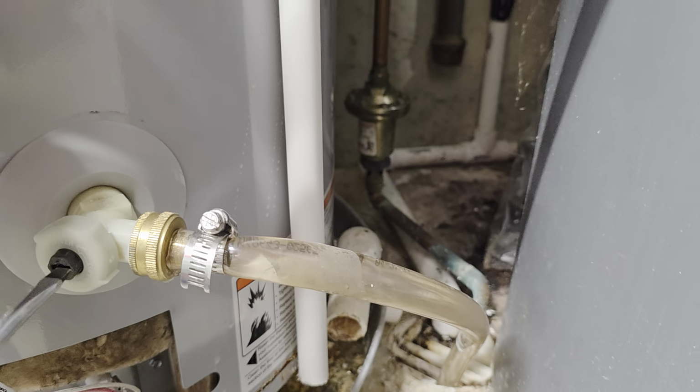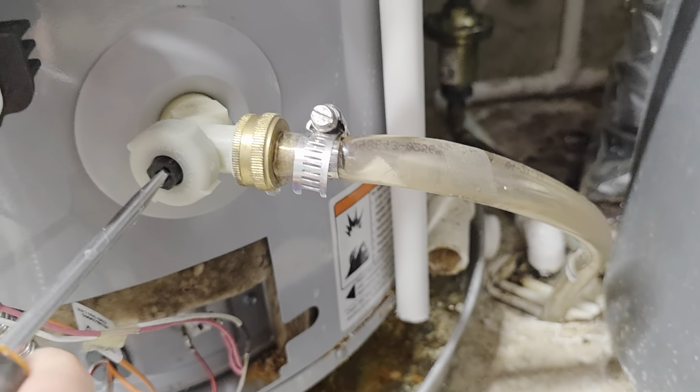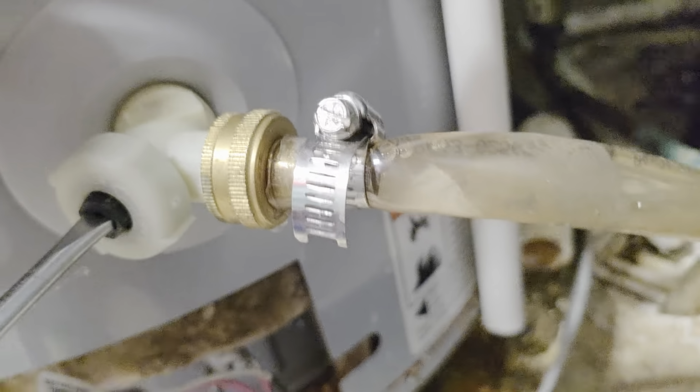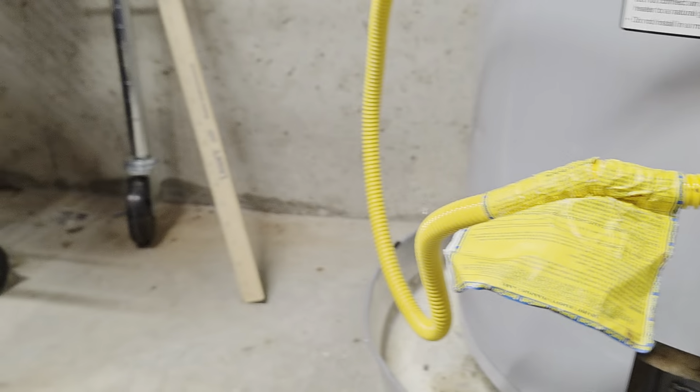Now, what I do next is, I'm going to go ahead and taper this off for a second. I'm going to let that settle for a second. Now, something else about sediment buildups inside hot water tanks is that since it's basically airless, there are no bubbles, no mass pushing, just basic pressure effect. So sometimes I've learned that if I give it a few minutes, more sediment will move from the middle of the tank down to the bottom of the tank because of the displacement coming from the bottom.